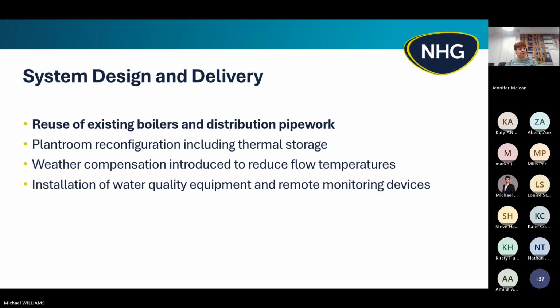So as some of you may know, the HNES scheme does not allow you to replace boilers because boilers are a non-eligible item. In this case, we were able to reuse the existing boilers and the distribution pipework, as mentioned earlier. The plant room was reconfigured to include thermal storage, and we introduced weather compensation measures to reduce the flow temperatures across the network. Also, a key improvement was to install water quality equipment and remote monitoring devices. So we installed a side stream filter, a vacuum degasser, and we installed remote monitoring of the water system through a device called HEVASure. Next slide, please.